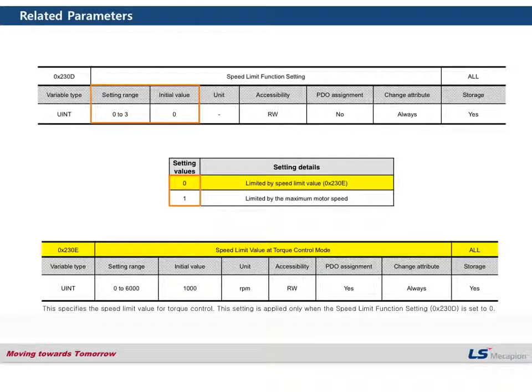Before we check the example for torque control, I'd like to inform you about two parameters that limit speed, because in torque control mode the speed limit is very important and necessary. Parameter 230D is to determine the way of speed limit. The first way is to limit speed by setting the value in parameter 230E.